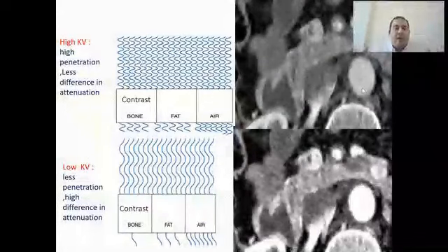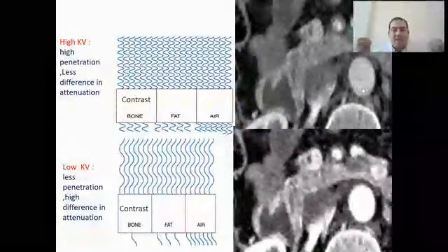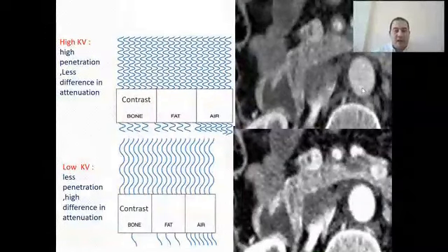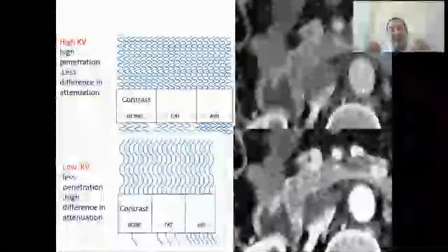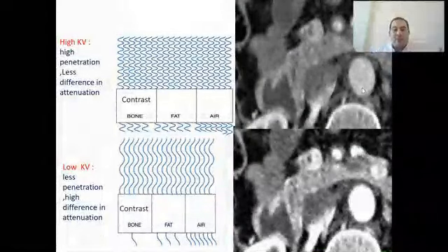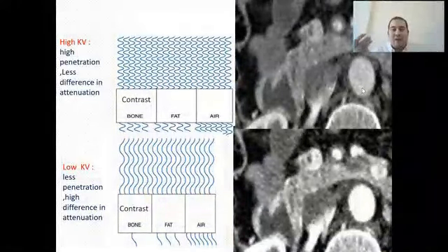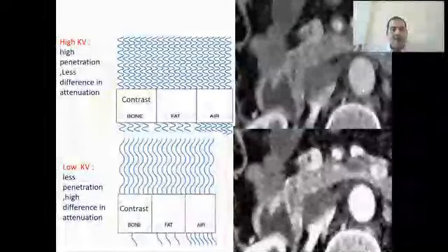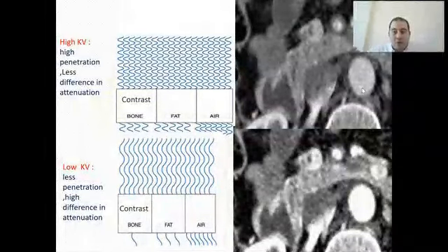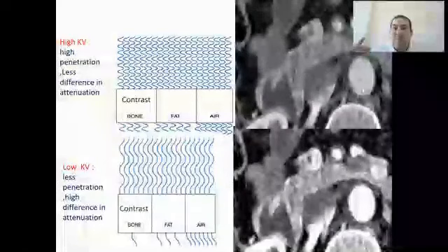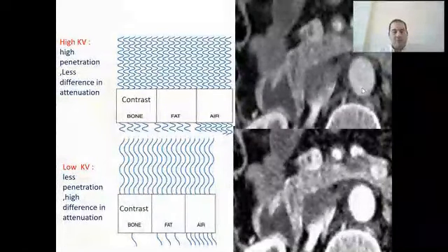The concept of the CT image itself relies on having contrast between the objects or the organs. This contrast occurs due to the differences in the various densities. So, how do I maximize this difference? By using low kV, because when I use low kV, the penetration power will allow my high density object to absorb radiation distinctly compared to the background.